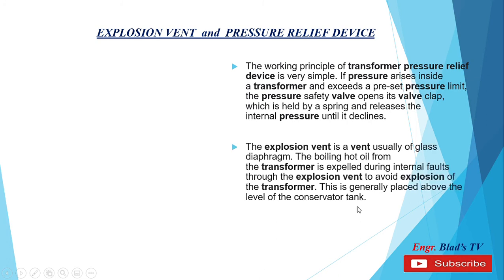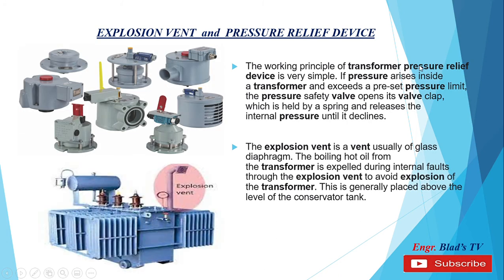Explosion vent and pressure relief device. The working principle of the transformer pressure relief device is very simple. When pressure arises inside a transformer and exceeds a pre-set pressure limit, the pressure safety valve opens its valve, which is held by a spring, and releases the internal pressure until it declines. The explosion vent is usually a glass diaphragm through which the boiling hot oil from the transformer is expelled during internal faults, to avoid an explosion of the transformer. This is generally placed above the level of the conservator tank. In this picture we can see the location of the explosion vent, which is located above the level of the conservator tank.